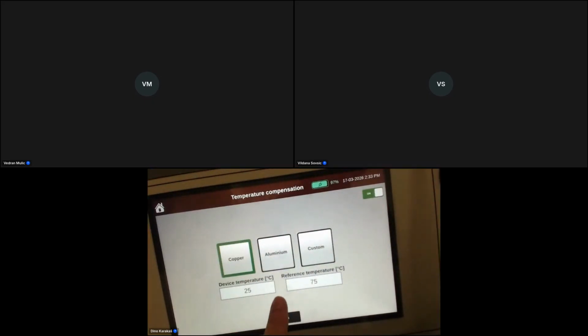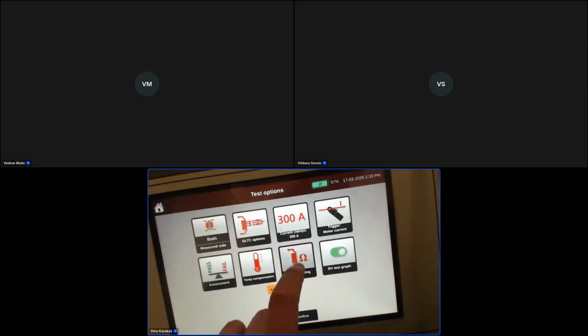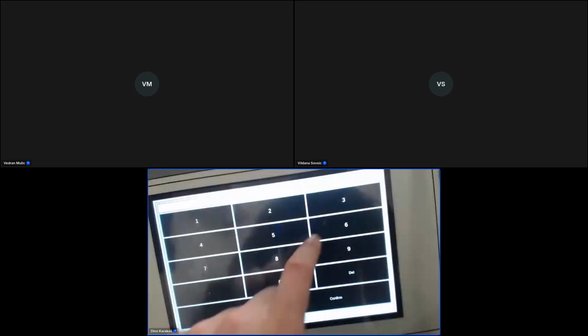Temperature compensation can be enabled. Here we will compensate it to 75. And winding resistance recording can be again manual or automatic. We will select automatic and we will say, for example, below 0.6% for 3 seconds to speed up the measurement a little bit in this case. We confirm it.